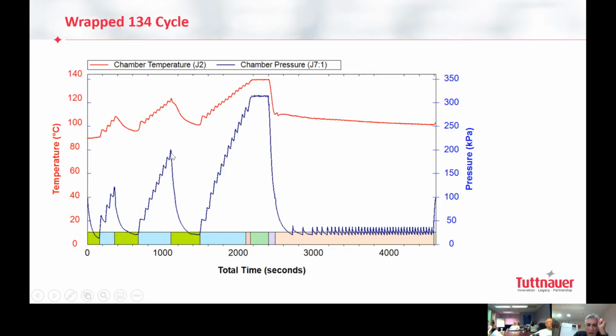This one is a bit higher in order to help start heating up the load, because you have to understand there are differences between loads. One load may weigh 100 grams, and the other one is 500 grams, the bigger one. So they will not reach the temperature at the same time. So what we're trying to do is get all of them coming to sterilization at the same time, and it's like this pulse. The reason we are going up above is to help this heating of the load and get a speed here when you go for the third time downwards to reach the third pulse. Because at the end, this vacuum pump, as I said, is a sensitive one because it's a membrane. So you have to be very sensitive, delicate with it.